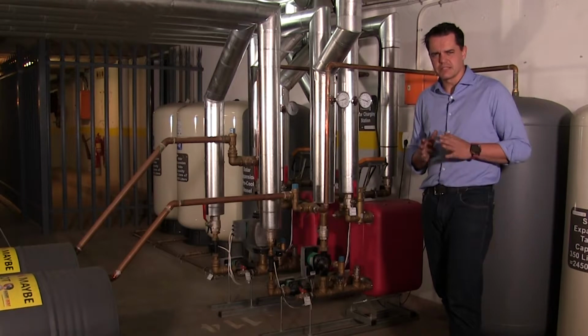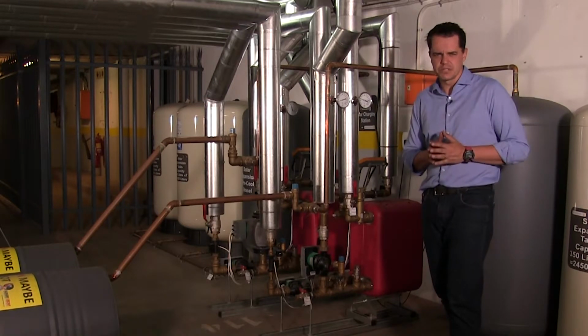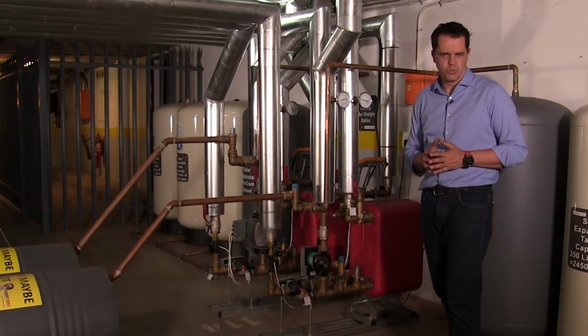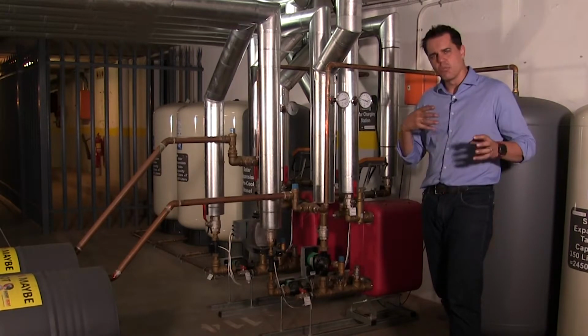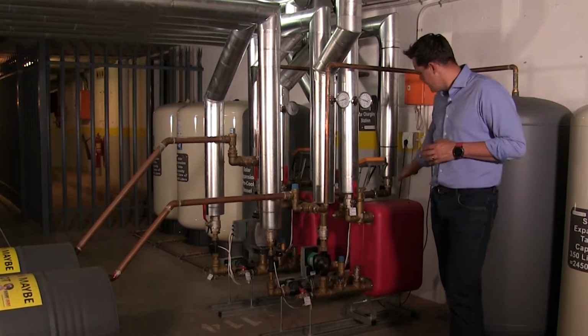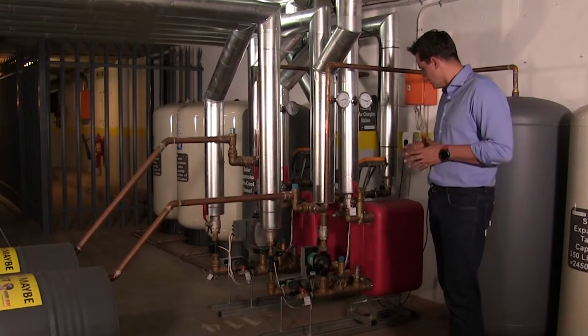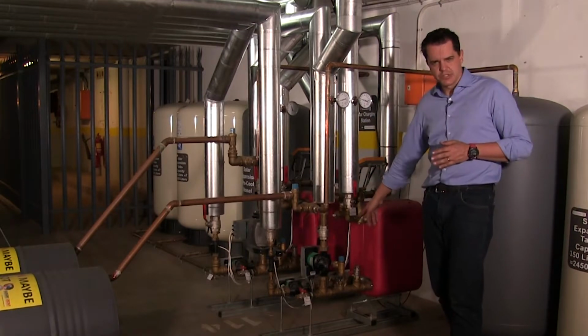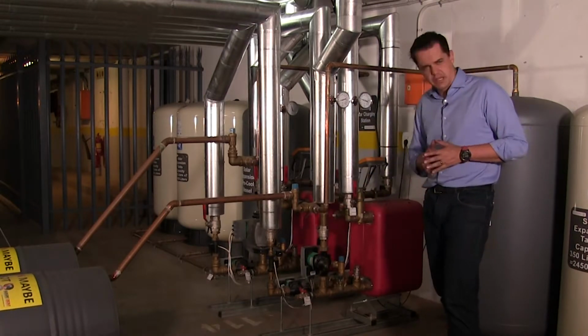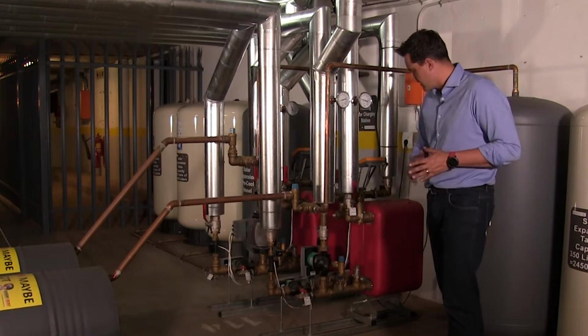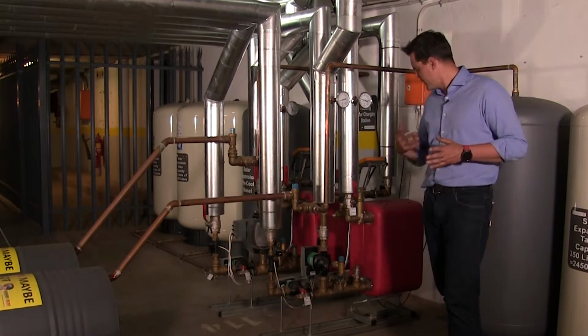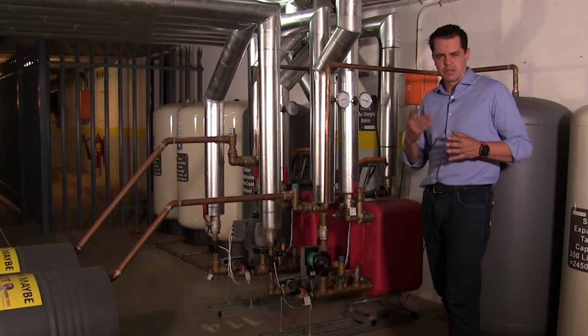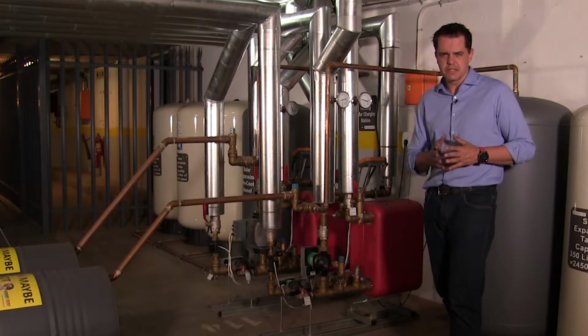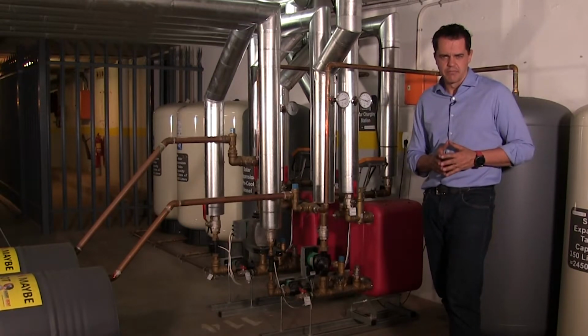It's an indirect system, so we've got a glycol loop on the solar side and we've got fresh water on the tank side. And the way that we transfer that energy is through the plate heat exchanger. On both sides we've got circulation pumps, and you can see the circulation pumps there at the bottom, the green, very high quality Wilo, and that circulates the liquids on both sides of the heat exchanger, transferring that energy.